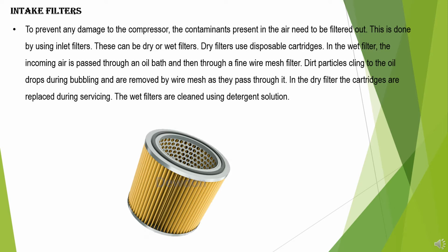In the wet filter, the incoming air is passed through an oil bath and then through a fine wire mesh filter. Dirt particles cling to the oil drops during bubbling and are removed by the wire mesh as they pass through it. In the dry filter, the cartridges are replaced during servicing. The wet filters are cleaned using detergent solution.